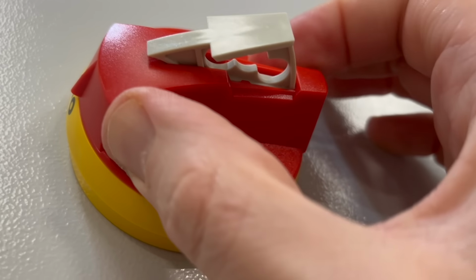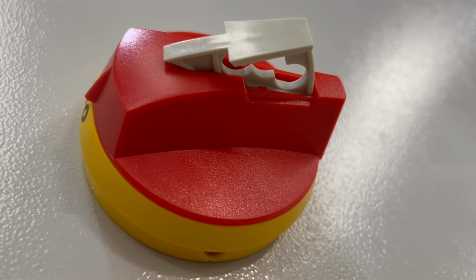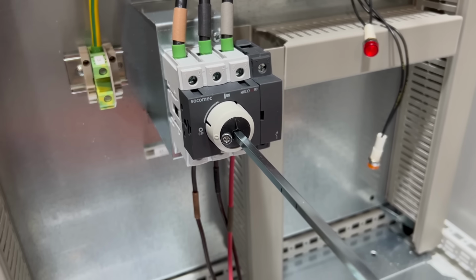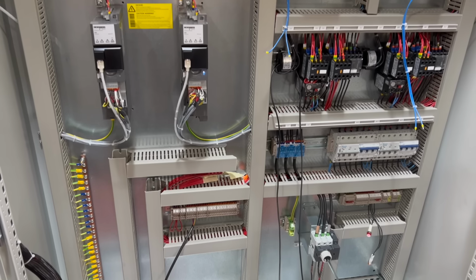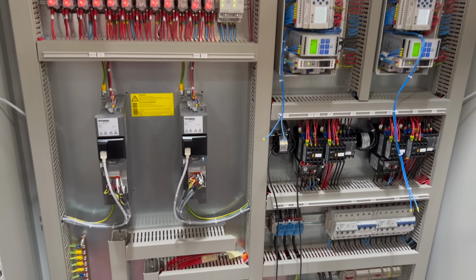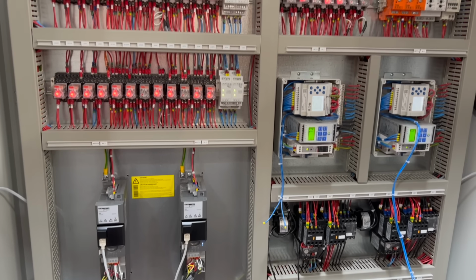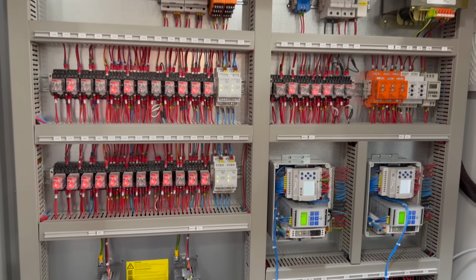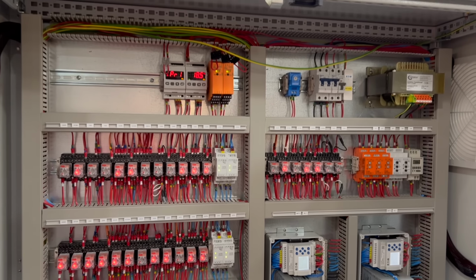be locked off. Now, you'll find it hard to believe, but some people will intentionally override the isolator by various means, which I won't demonstrate here for safety purposes. They do this so that they can monitor the devices in here, perhaps testing live terminals to see if they're powered up when they should be, or looking at indicating LEDs and readouts. Let us know in the comments if you think that's recklessly dangerous, or if the necessity justifies the risks.